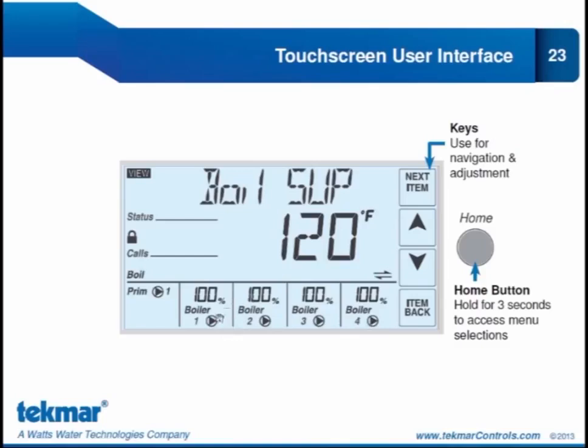You'll see on the screen too, we have boiler 1, boiler 2, boiler 3, boiler 4. And right now it shows 100% for all of them. You might guess that you can actually see the output of each of the boilers on this screen, and you would be correct. If you have a single stage boiler, it will show up as 100% output. If you have a 2-stage on-off boiler, if only the first stage is on, it'll show up as 50% output. If stage 2 is on, it'll show up as 100% output. If you have a modulating boiler with a firing rate target, the percent modulation will appear here. And if it is a temperature-based target using the EMS1 or the EMS2, you will see the temperature.